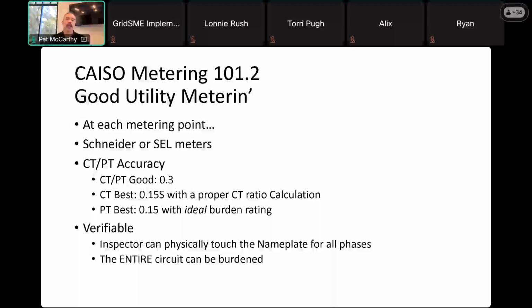In terms of saving money in the design space, a lot of folks like to think: oh, I've got a transformer with a couple of CTs I'm not using in a bushing, or a breaker somewhere with bushing current transformer space I'm not using - I can just stick my metering stuff there. Sometimes that works. If you're thinking about putting it in a transformer, don't - I've never seen that work well, not one time. Circuit breakers, it depends, and it comes down to how accessible the current transformers are.